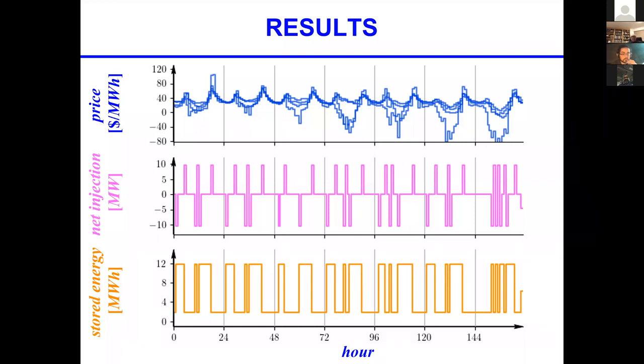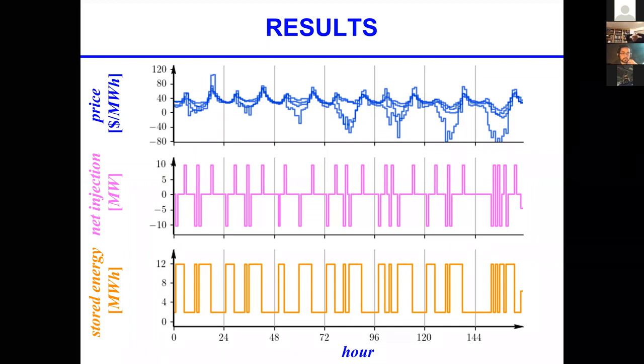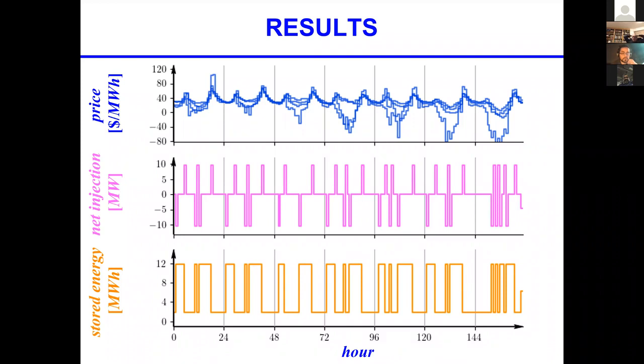It has a capacity of 20 megawatts. So it would be over the hour duration for it to change from the energy shown to the energy it goes down to or up to. It doesn't happen instantaneously the way you draw it. So these are all values for one hour, sampled for one hour. Yes, but I'm trying to tell you that in an hour you have this drop from 12 to 2 instantaneously, and it can't happen that way.